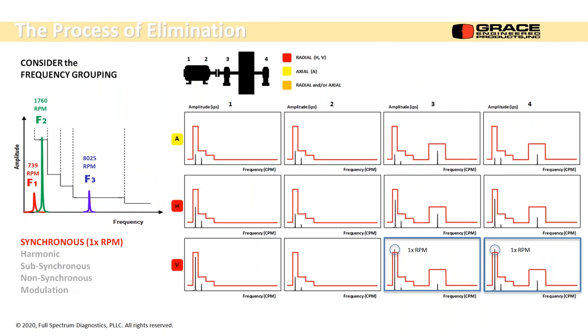This is how we would commonly take our data, and it usually goes into a database, and the database applies the alarms and tells us what's bad. And right now, it would shoot out an alarm report that would say our 1 times RPM peak in position 3 on the shaft, so the fan bearing 3, fan bearing 4, they both exceed the criteria in the vertical direction on those two bearings. So that gives us some good information to go and hunt for what the problem is.